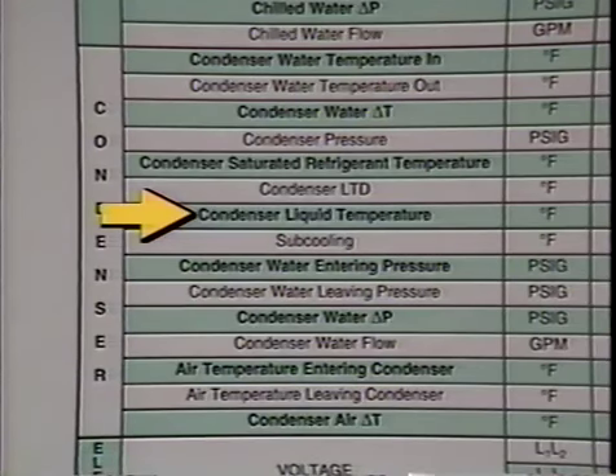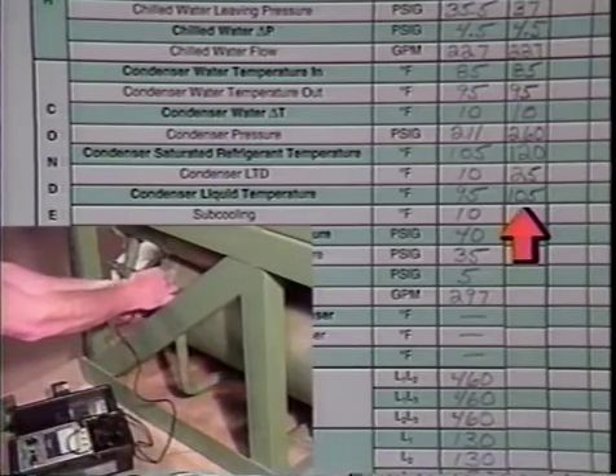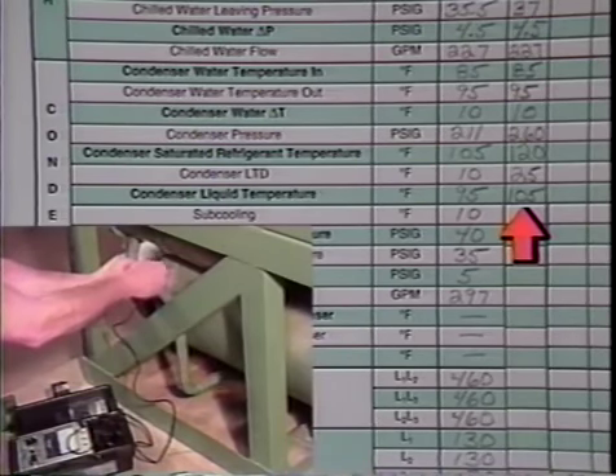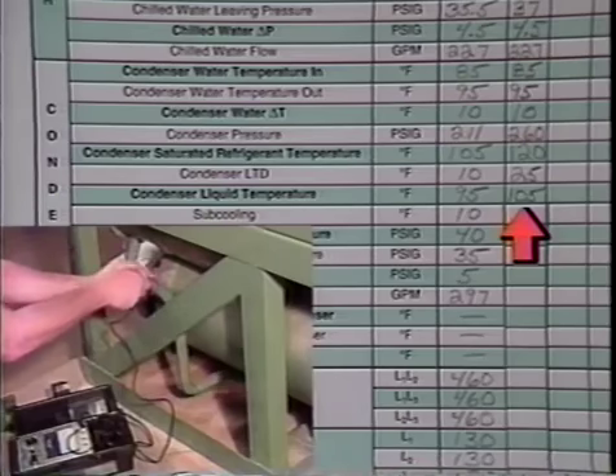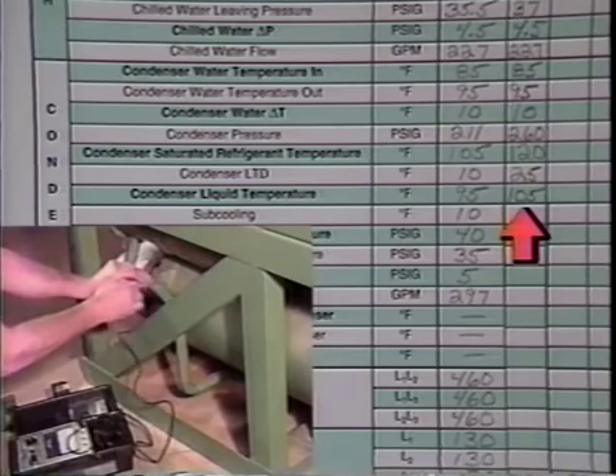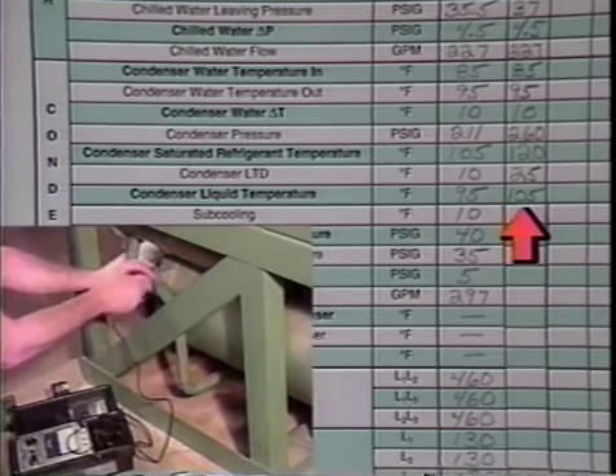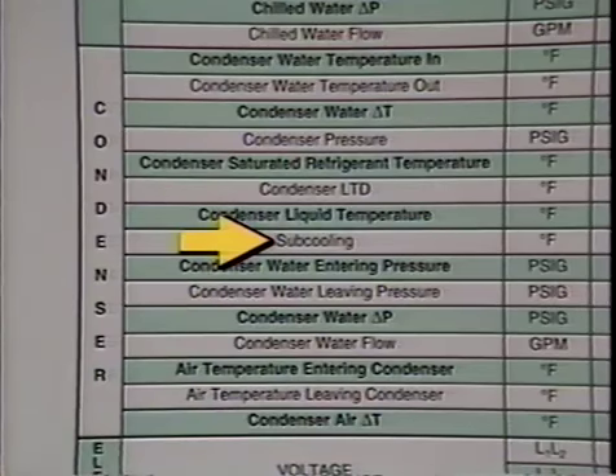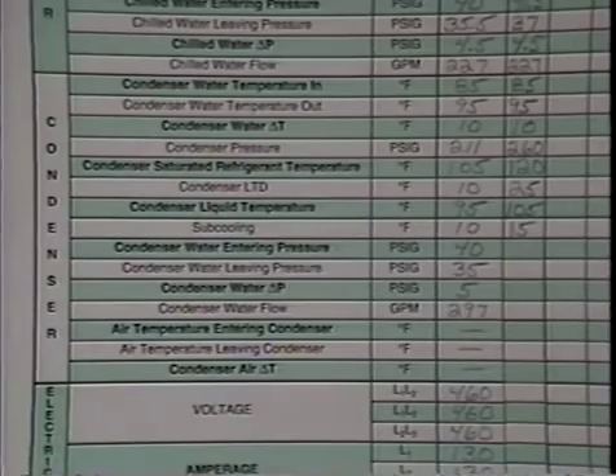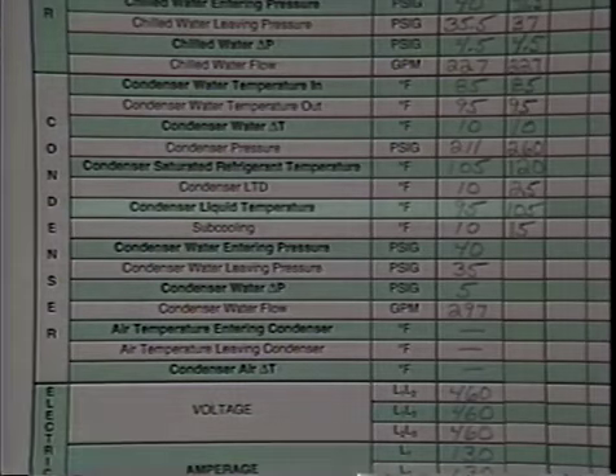Condenser refrigerant liquid temperature. Measure the condenser refrigerant liquid temperature. If a thermometer well or control panel display is not provided to do this, strap a digital temperature probe on the bottom side of the liquid line. Subcooling. The amount of subcooling can now be found by subtracting the liquid line temperature from the condenser saturated refrigerant temperature.